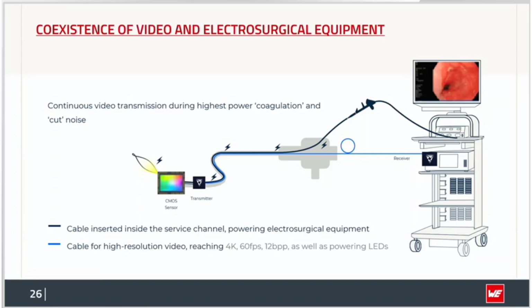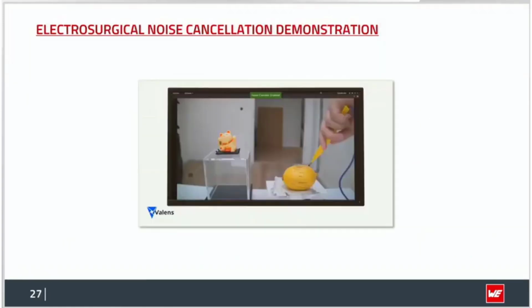And especially when this is used during endoscopy, there's a coupling between both cables, which are lying in parallel inside the endoscope. You can see here the black one is the cable used for powering the electrosurgical equipment, and the blue one is the cable which is powering the camera and also the LED light, and which is also transmitting the high-resolution video, in this case 4K 60 frames per second. And I can show you a demonstration inside the video of how this setup is working with the noise canceller enabled and with the noise canceller turned off.